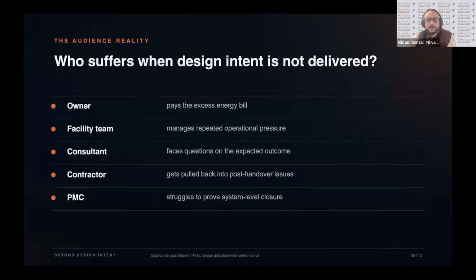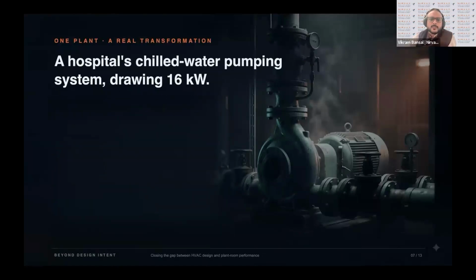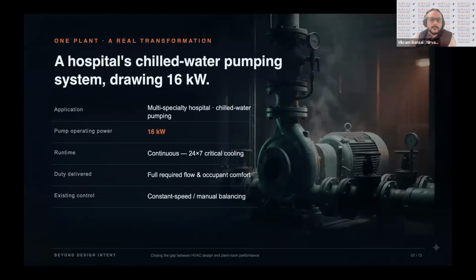We worked on one of the hospitals where there was a pumping system we were measuring. It was taking 16 kilowatts at part load. And what we found was that it was running 24 by 7, being a hospital. It was working at the full required flow and occupant comfort was there. Though it was a variable pumping system, it was running in manual mode. The VFD was modulated by the operator, not by any automatic controls.